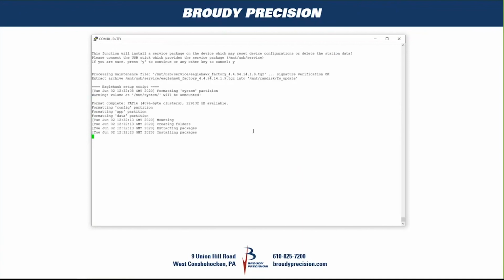One thing I found this morning in doing some more testing with this was that when you go through this process and restore it back to 4.4, I then went in and commissioned it with 4.8 with a station. Everything went through fine, but there was one platform serial service file that didn't get installed, like in a video I made a month ago, that the serial ports are missing.